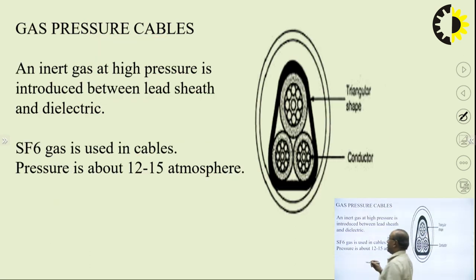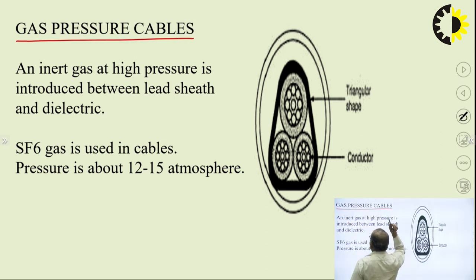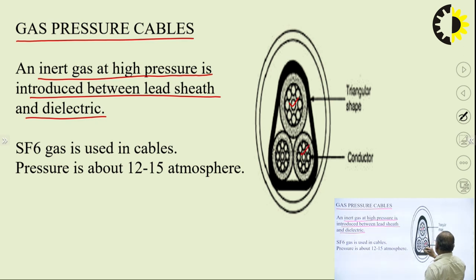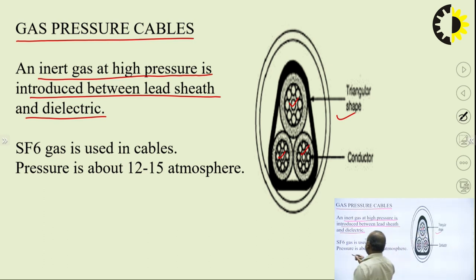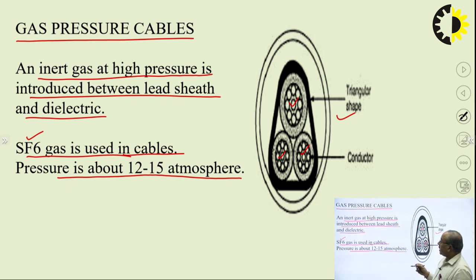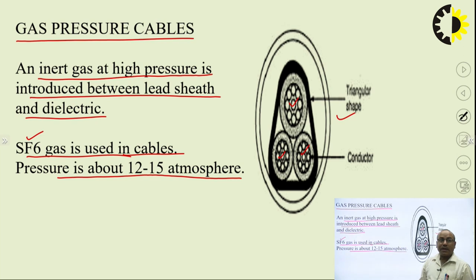The next type is gas pressure cable. These cables use an inert gas at high pressure, introduced between the lead sheath and the dielectric. The gas used is SF6 — sulfur hexafluoride — and the pressure maintained is approximately 12 to 15 atmospheric pressure. That is why these cables are known as gas pressure cables.